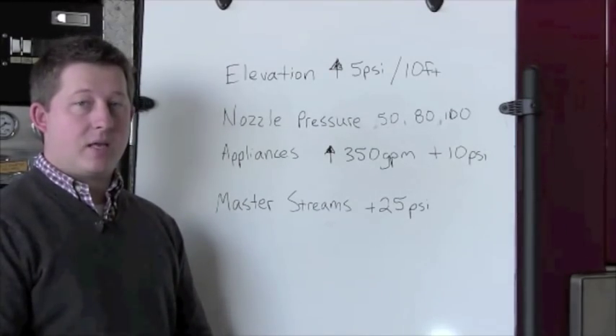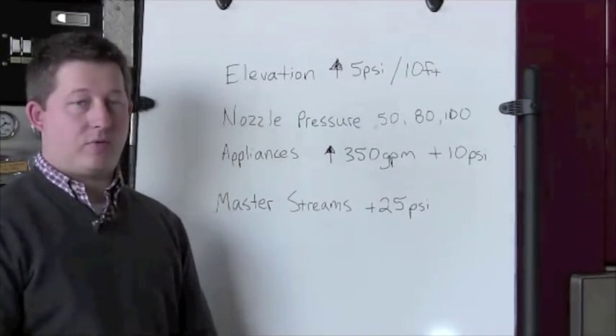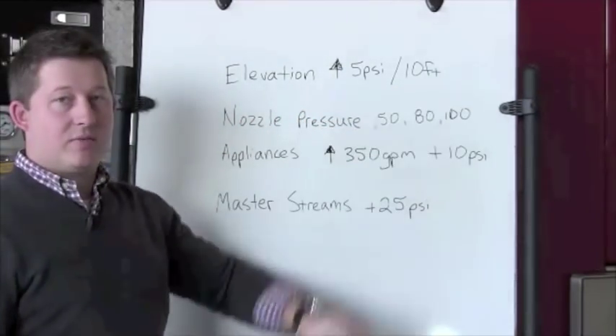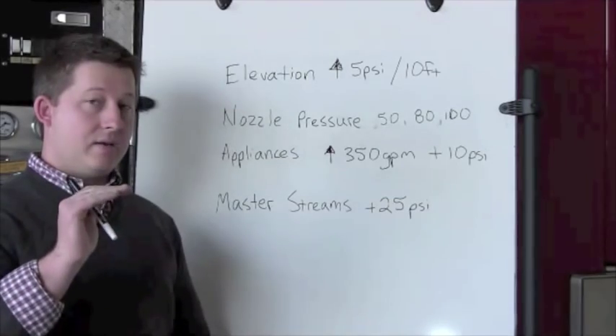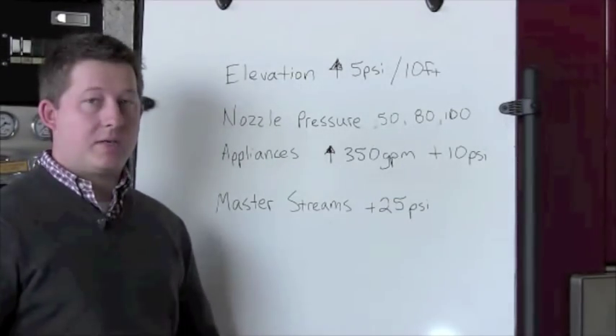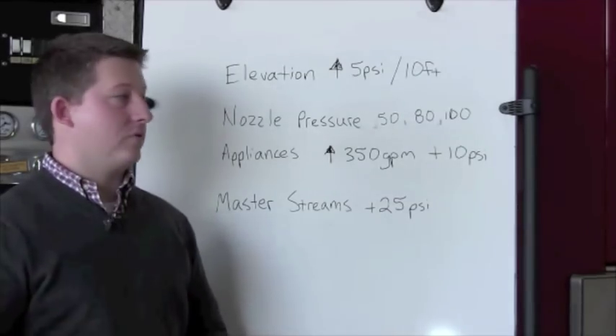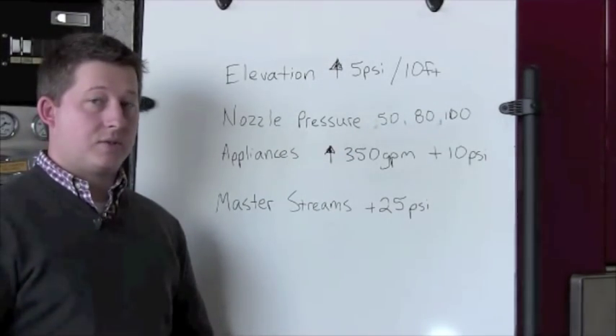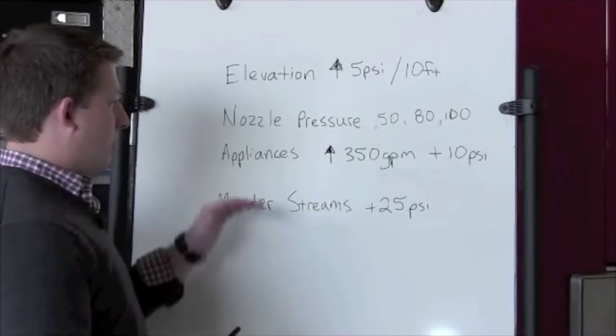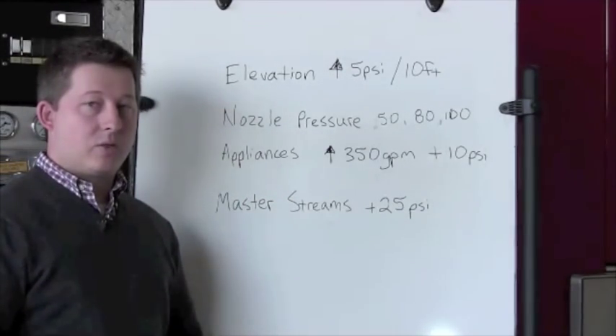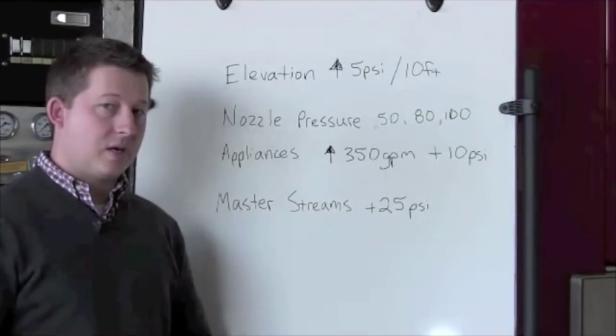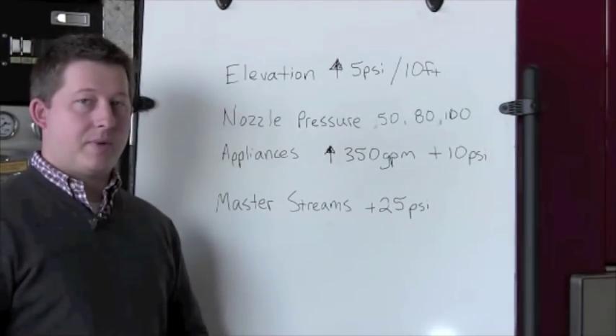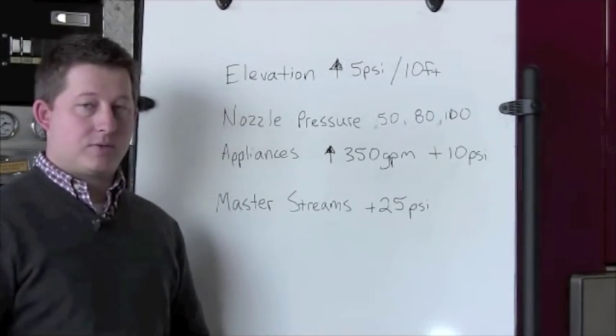Here's a list of things to keep in mind when calculating pump discharge pressure and friction loss. For elevation pressure, add 5 psi for every 10 feet, or divide the height in half — and for a high rise, don't count the first floor, only count the floors above the first. Nozzle pressure is usually 50, 80, or 100 psi, but many nozzles operate at 75 psi. For appliances, if you flow more than 350 gallons per minute, add 10 psi for friction loss — that's a rule of thumb. For master streams, add 25 psi of friction loss.